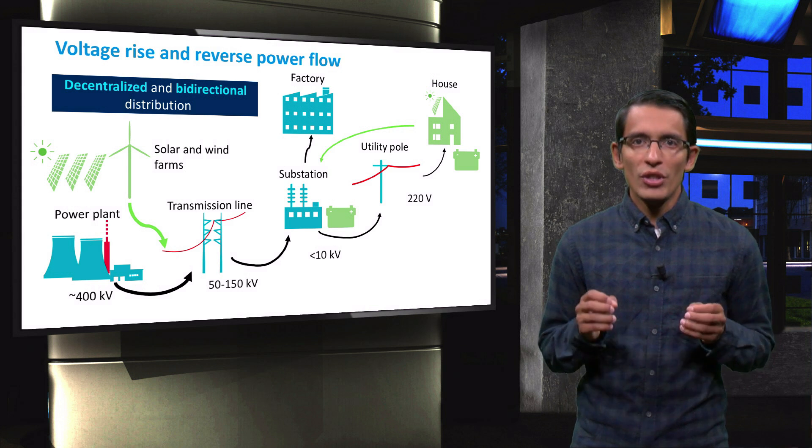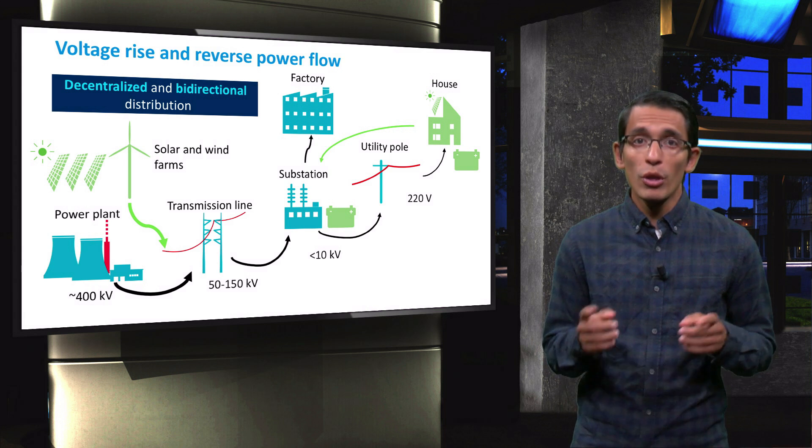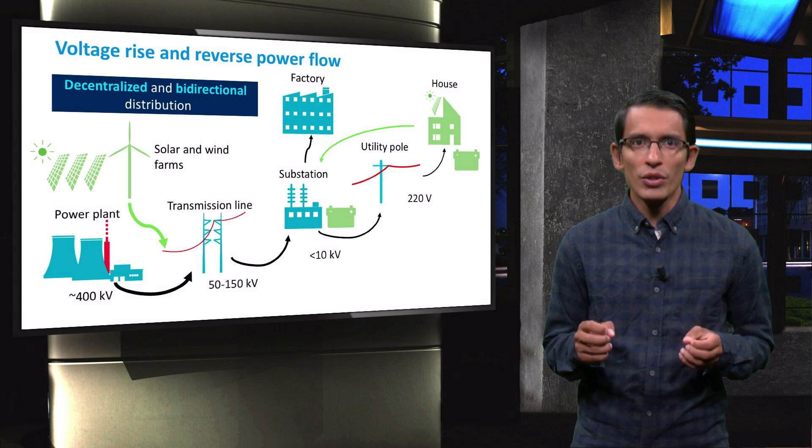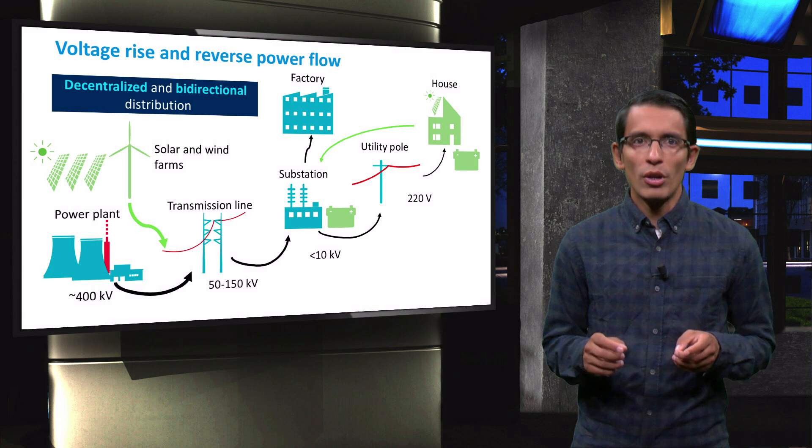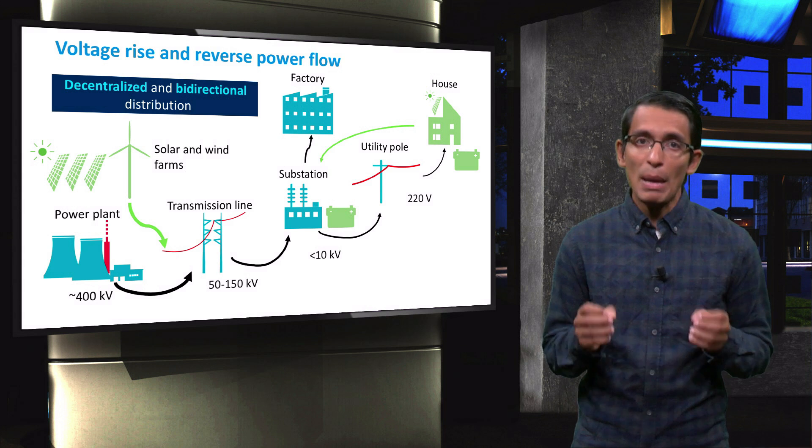If distributed generation systems result in a reverse power flow through the regulator, tap changing control systems in the transformer which regulate the turn ratio and therefore the voltage inputs and outputs may become unstable.